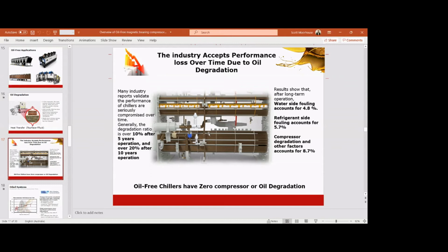And with all these reports on the market today, it's considered that the waterside fouling accounts for 4.8% of that derating, which will be common on an oil-free machine and a lubricated machine. The refrigerant side fouling accounts for 5.7% of the fouling over that period of time. And the compressor degradation and other factors account for 8.7%. So this can be rotor wear on a screw if the bearings haven't been replaced at an acceptable time, etc. So these are the sort of numbers that we're putting down for degradation over a period of time.